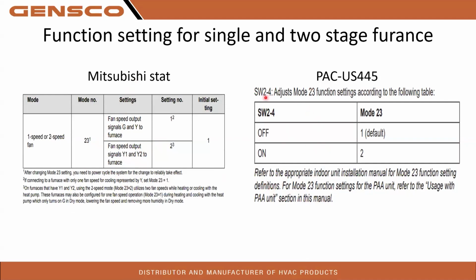So if you have a two-stage, SW2-4 needs to be turned to the on position. If you don't do this and you have it set up and wired for a two-stage and you don't flip this switch on, you are never going to get W2 or Y2 to turn on. So you're always going to be running a low fan speed and you're going to have cooling and capacity problems. Okay, so very important, if you're using two-stage, make sure to program these things. You know, I see some guys that don't know about this and just do jumper wires from Y1 to Y2. Honestly, you're probably better off doing this route. It's really easy and you get more functionality and efficiency out of your equipment. So if you can, do this instead.